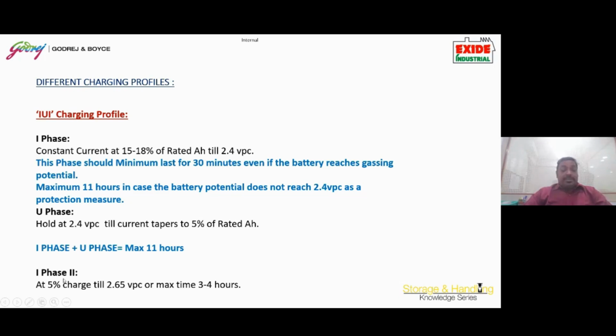Then in phase 2, we charge with the current at 5% till 2.65 VPC, or a maximum time of 3 to 4 hours. So after 2.4 is achieved, we reduce the current to 5%, and then we can stabilize the current at 5% up to 2.65 volt per cell maximum. 2.65 to 2.7, anywhere it is okay.